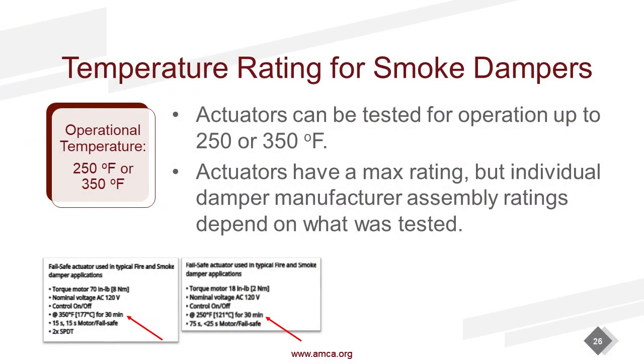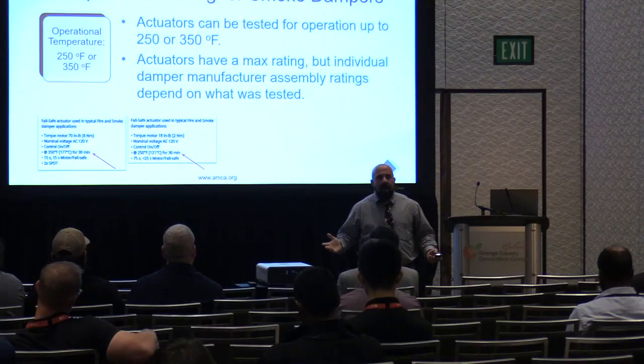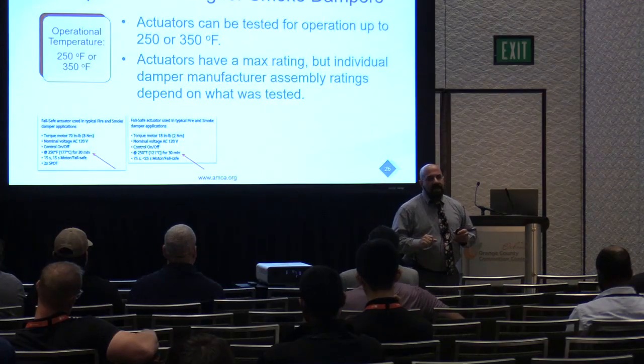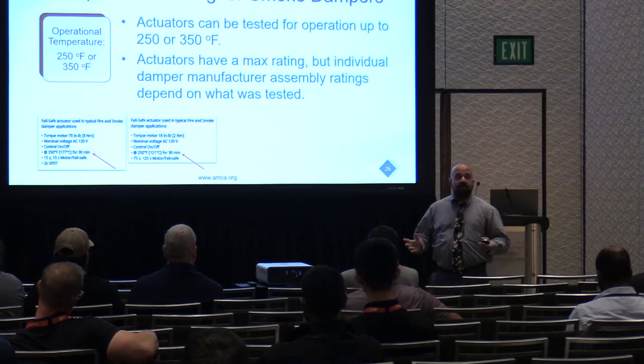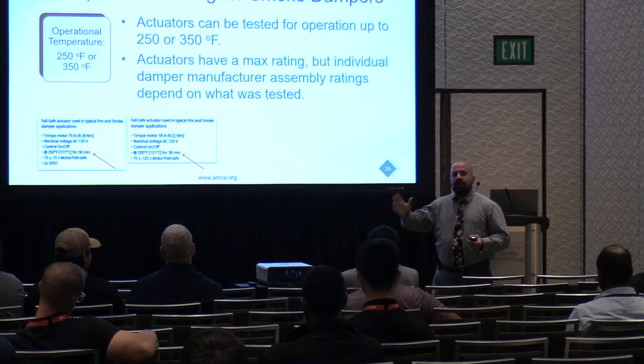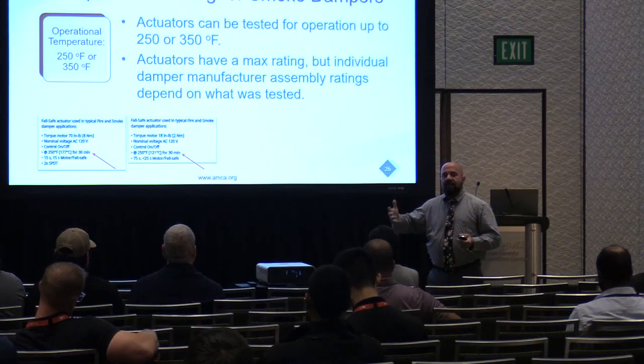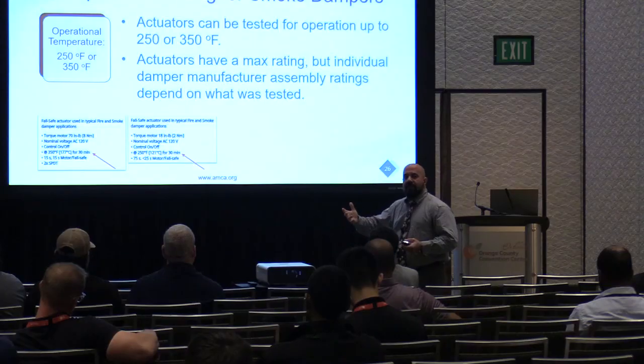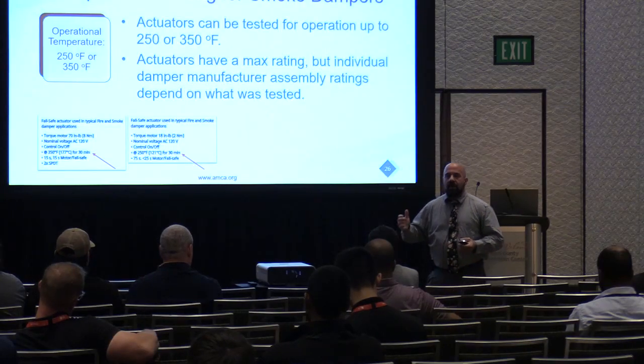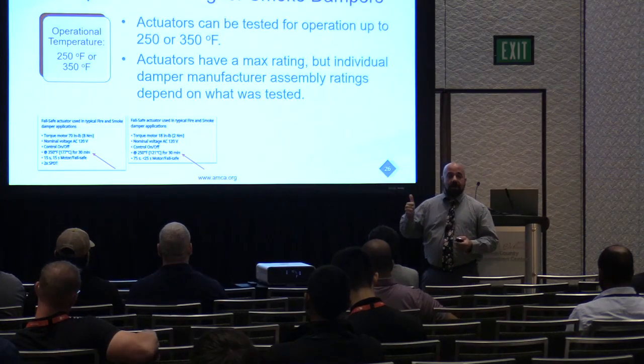The only time we really should be seeing 350 rated dampers is if I have other high temperature rated equipment in a smoke control system. My fans are high temperature, other high temperature rated equipment, we want our dampers to have the same rating. But if I don't have anything rated for high temperature, and we do what I call the garbage can spec, and we just say, well, 350 is better than 250, all you did was just create a more expensive damper. In order to get to 350, the torque rating of the actuator has to go up, which means your cost is going to go up.